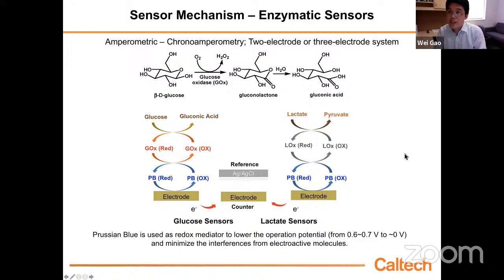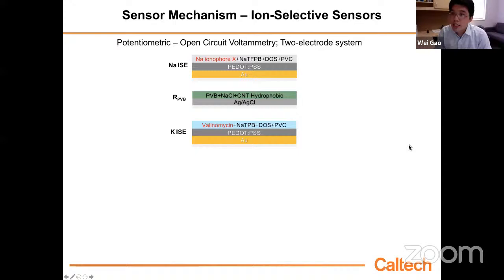If you want to detect ions such as sodium, potassium, or calcium, we typically use an ion-selective electrode—a two-electrode design. We have a working electrode, say a sodium ion-selective electrode or potassium ion-selective electrode, and we measure the voltage difference between this working electrode and the reference electrode. On the ion-selective electrode, we coat the electrode with an ion-selective membrane. A key chemical here is the ionophore. For sodium, we use sodium ionophore X; for potassium, we use valinomycin. This specific ionophore introduces the selectivity.